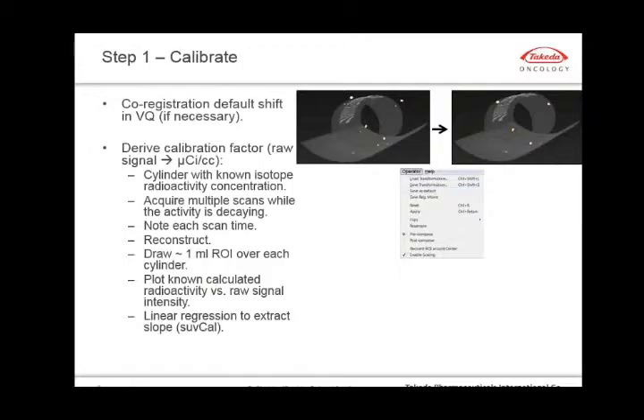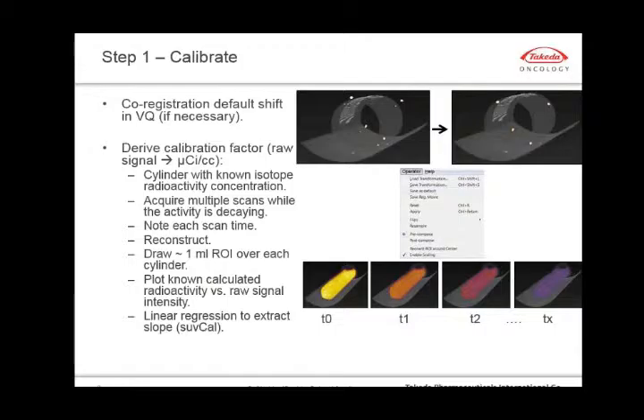As a result, every time we subsequently load a PET-CT dataset into VivoQuant, it will automatically be co-registered. The next calibration we derive is a calibration factor to help us derive quantitative data — to convert raw counts per CC from the image into microcuries per CC. For this, we inject a known amount of radioactivity in a conical tube containing water, acquire several scans over time as the radioisotope decays, draw ROIs of consistent volume on the cylinders, plot the expected radioactivity against raw counts, and by doing a simple linear regression extract the SUV calibration factor. We don't do this for every study — only after scanner maintenance or when something changes.